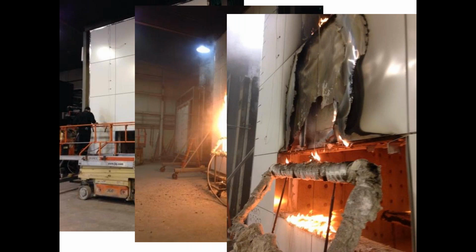The combustible cladding might catch a thermal spacer on fire, and the thermal spacer might provide more fuel and contribute to the cladding spreading its fire, but no, that didn't happen. But the reason for selecting it was to select something that was the most aggressive situation.